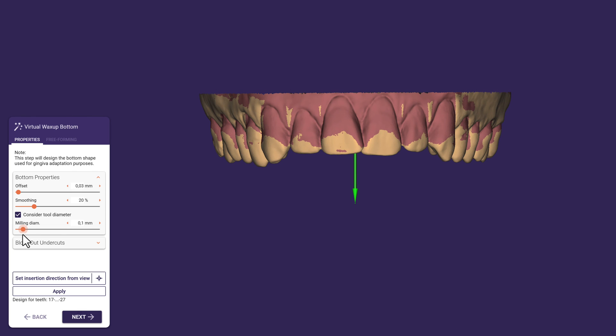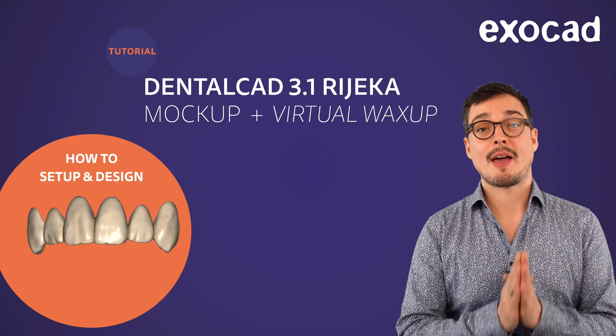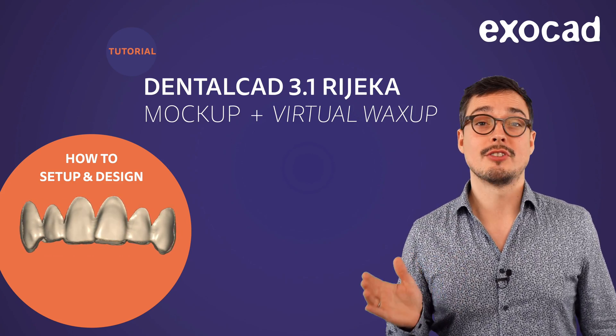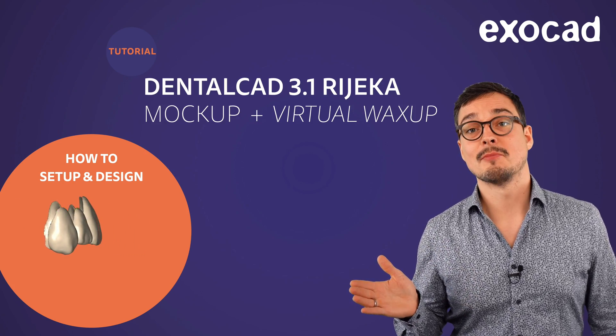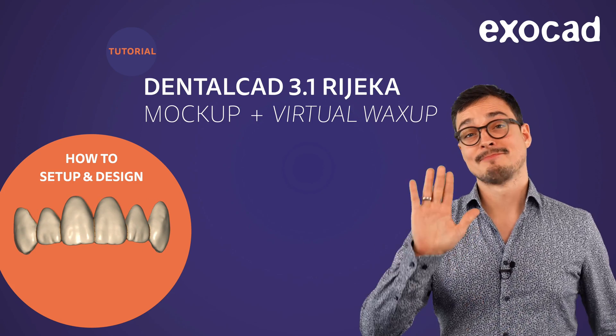Let's continue with the Block Out Undercuts tab. The angle specifies the amount of draft angulation in relation to the insertion axis. Allow undercuts to regulates the maximum amount of retention — higher values increase the depth of the retention area, resulting in a stronger fit. But take into account that strong undercuts may result in tension on the teeth and could damage the thin mockup. Now you know all the parameters in detail to manufacture a beautiful and precise mockup. You will also benefit from what you learned today when creating a bite-splint or anatomical bite-splint, because you will see all these parameters again. We hope you enjoyed this video tutorial and hope to see you soon.